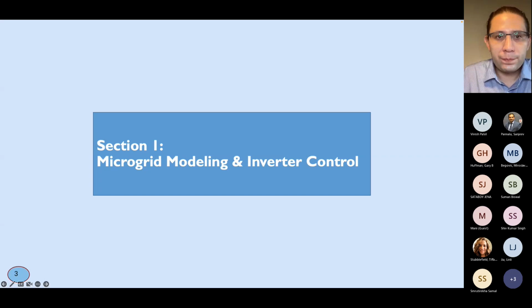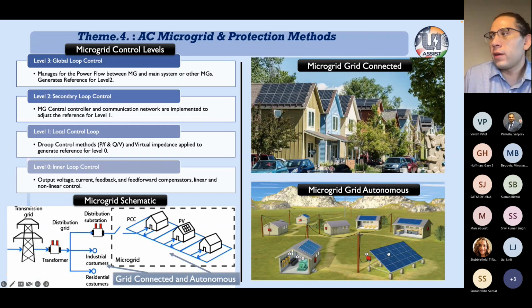To continue further, I will talk about the first topic, which is microgrid model and inverter control. As we are all aware, we know what a microgrid is. In summary, we have a microgrid that can operate, as we can see in the top figure. We have 4 levels of control of the microgrid. Level 0 is the inner loop control for inverters. Level 1 is the local control loop, most common for the droop control. The second level is the microgrid central control. And the third level is the global loop control that works with the grid in a big setting.